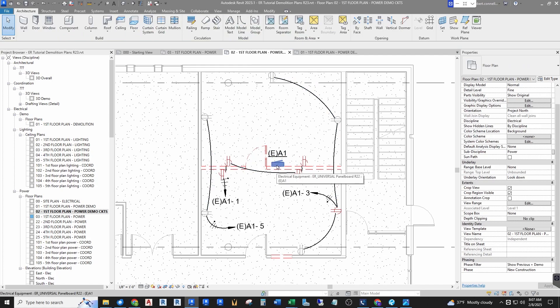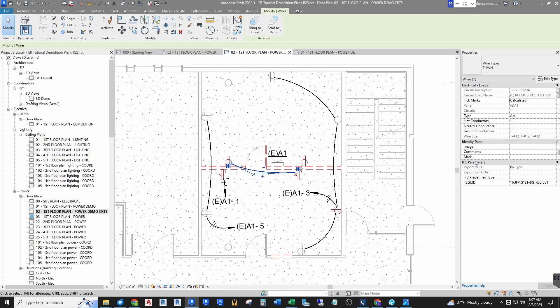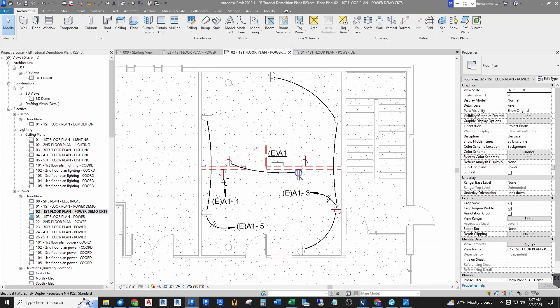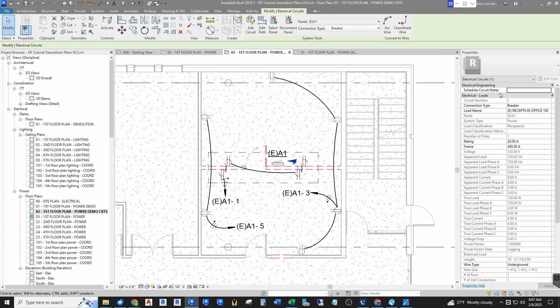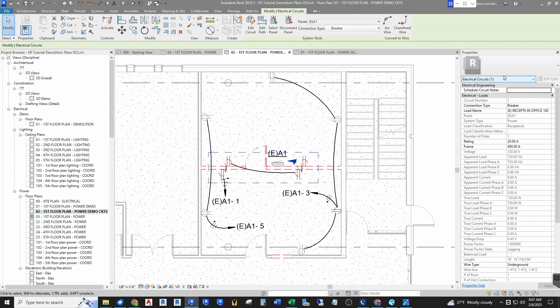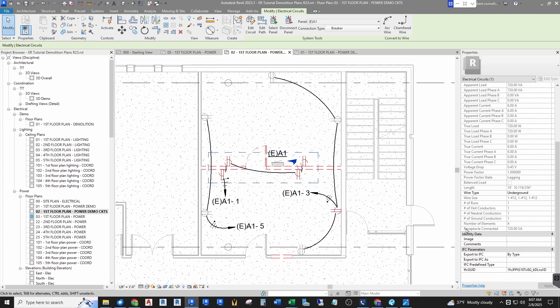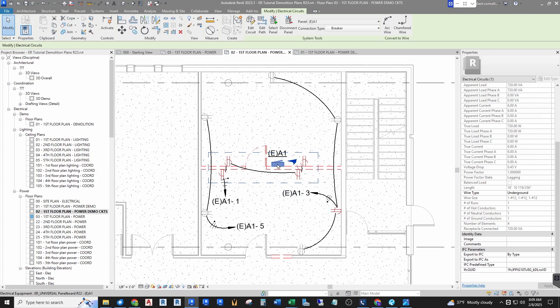What it means is the properties of the circuit isn't being demoed—there's no phasing information for a circuit. It sees the circuit remaining but the panel doesn't match the phase of that, so we get this problem and it wants to disconnect everything. Therefore I cannot show existing circuiting to a panel that I'm removing, and then I also can't have these circuited to the new panel as well as to the old panel. So if you click on a wire there's no phasing. If I hover over with tab to get to the circuit, click on the circuit, now I'm looking at electrical circuit—again there is no phasing data. So there's a missing element in Revit and this has been brought up numerous times on various Revit and Autodesk sites that circuits are missing phasing information.